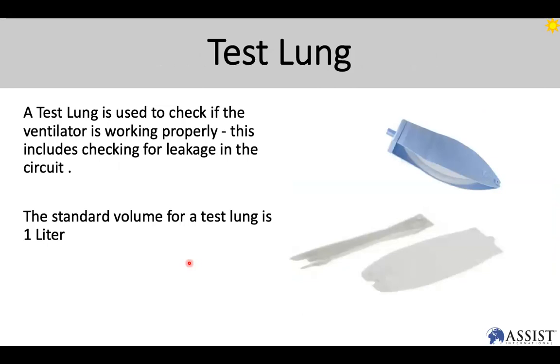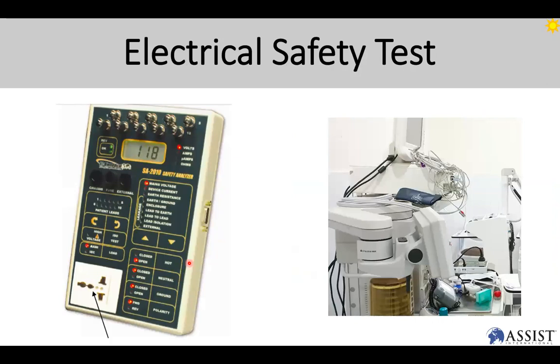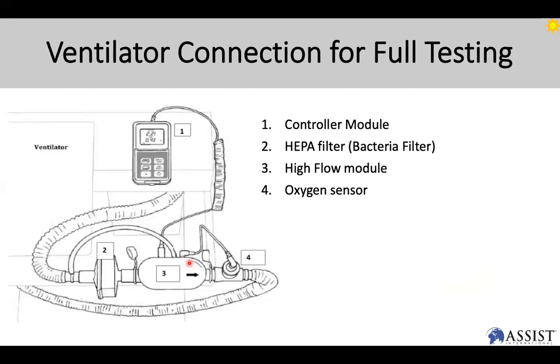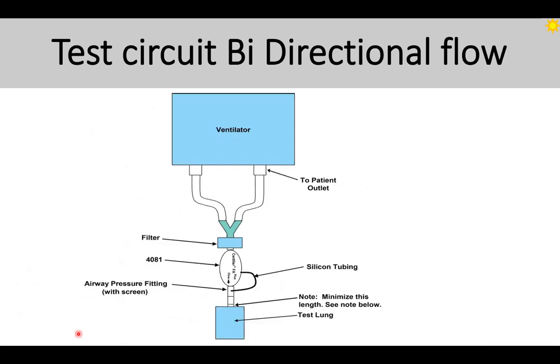The test lung is used to check if the ventilator is working properly. This includes checking for leakage in the circuit. The standard volume for a test lung is 1 liter. We will go through the test setup so you can all refresh your memory. Here's a test setup of all of the pieces we've talked about. You've got the controller module for your vent analyzer that connects to the high flow module. You'll have the HEPA filter. You'll have the oxygen sensor. And so you'll see that the inspiratory limb will be connected this way. And the expiratory limb will be connected from there on.